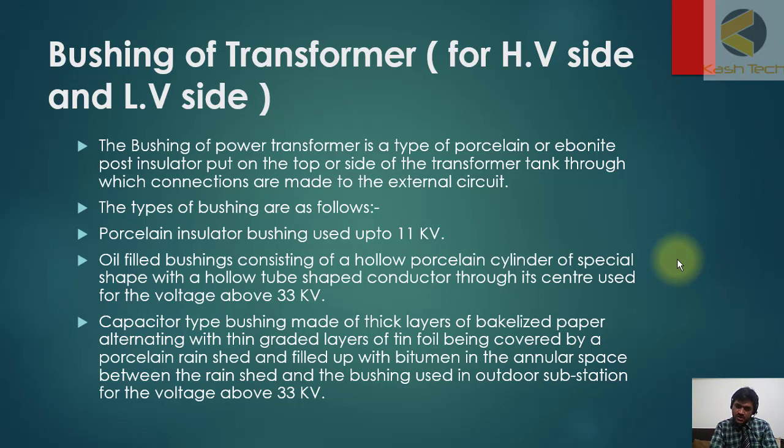Capacitor type bushing made of thick layers of bakelized paper alternating with thin graded layers of foil, being covered by a porcelain rain shed and filled up with bitumen in the annular space between the rain shed and the bushing, used in outdoor substations for voltages above 33 kV.